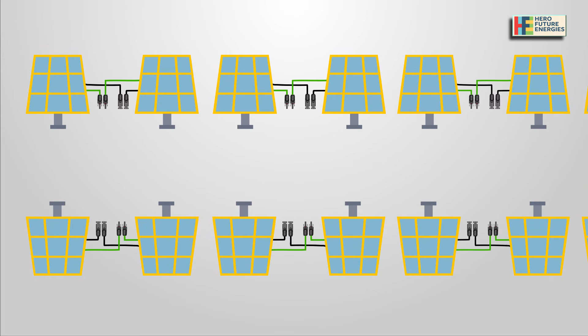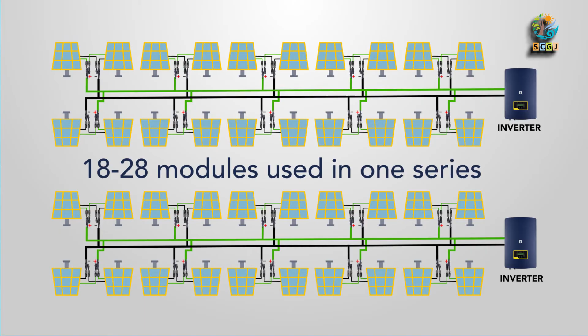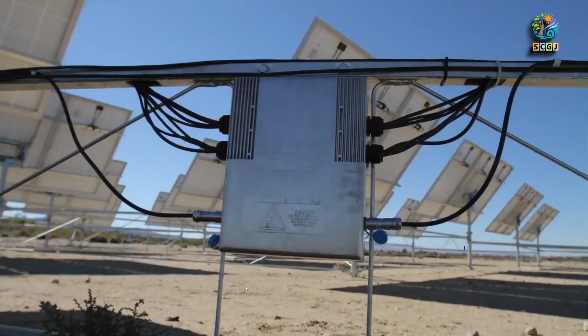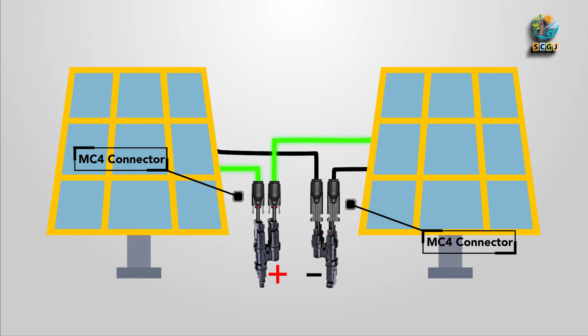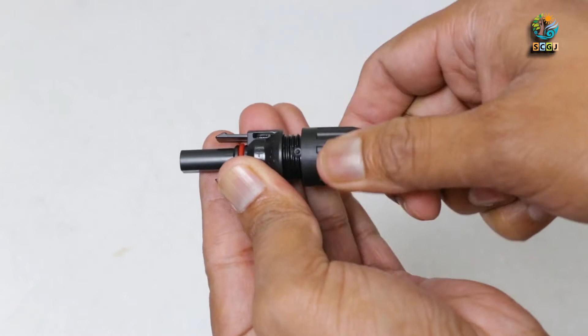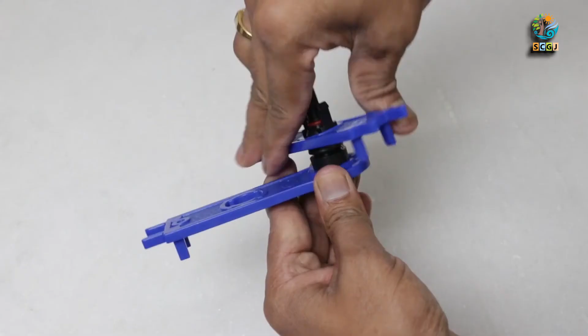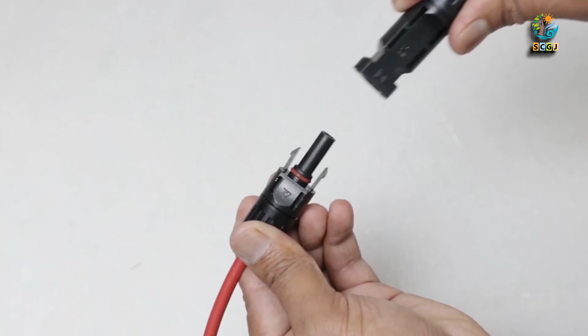Now comes the critical step of forming a panel string, which entails wiring a group of panels into a single input on the inverter. Usually 18 to 28 modules are used in one series. After string formation, you wire the solar modules using MC4 connectors. In a series connection, you connect the positive wire from one module to the negative wire of the other. As a good industry practice, rotate one of the tools while keeping the other still to finish tightening the MC4 connector.